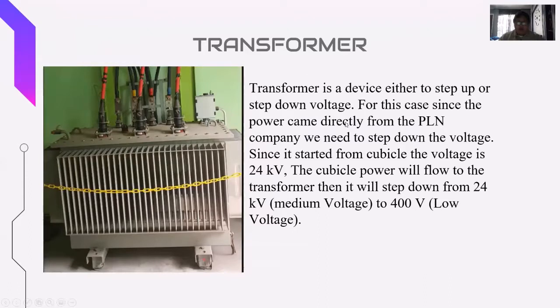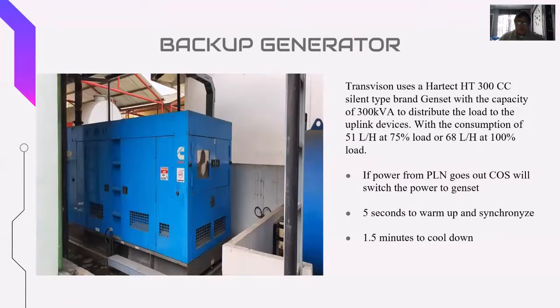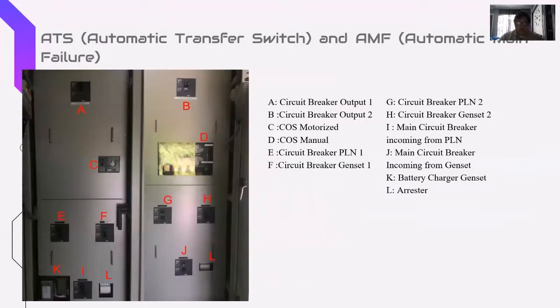Then the transformer, as I said before, is a step-down transformer, which steps down the 24 kilovolts that we get from the panel, from the PLN, to a low voltage, which is 400 volts. Then the backup generator: the genset that Transvision uses is a Hartect HT 300 CC silent type genset with a capacity of 300 kilovolt ampere to distribute the load to the uplink devices, with a consumption of 51 liters an hour at 75% and 68 liters an hour at 100%. As I said before, if the power from the PLN goes out, the COS will switch the power to the genset, and it will take 5 seconds to warm up and synchronize and 1.5 minutes to cool down when it is turned off.